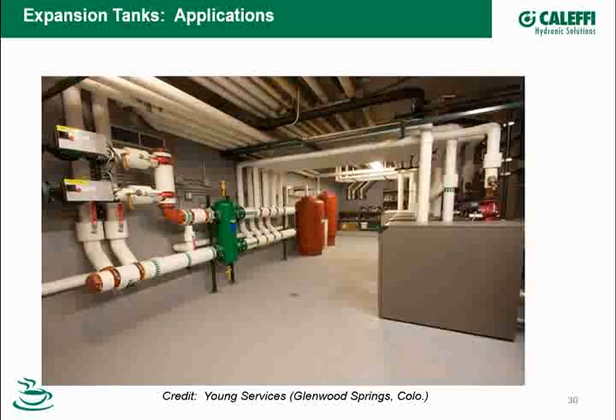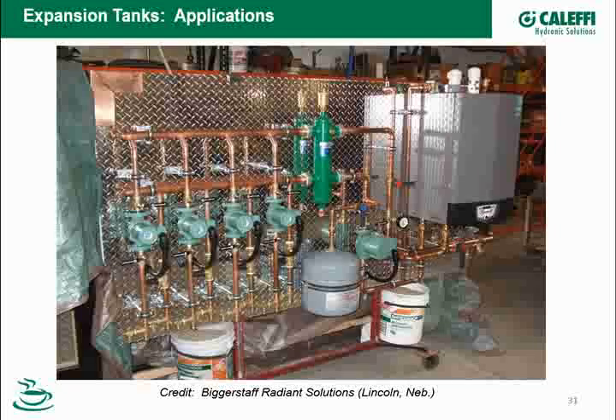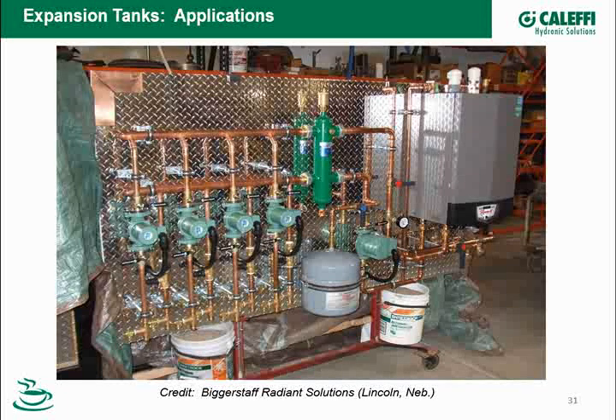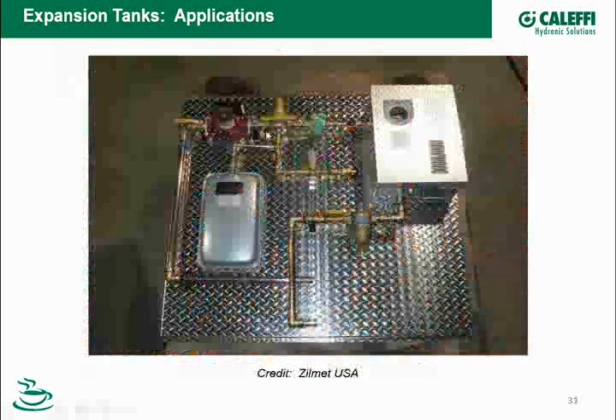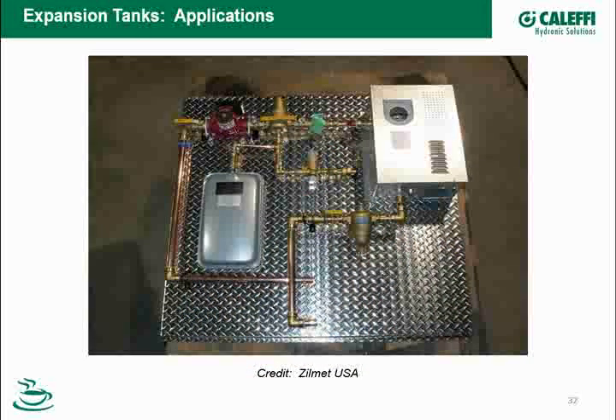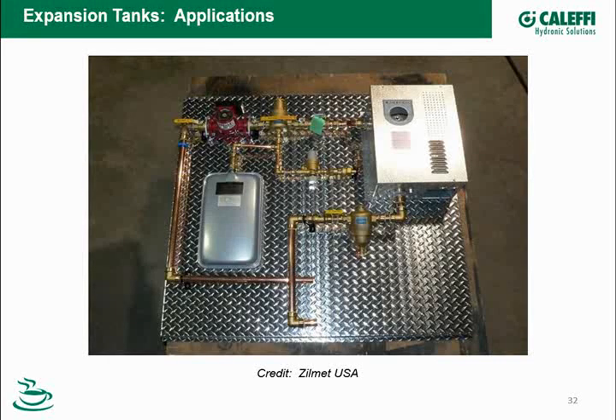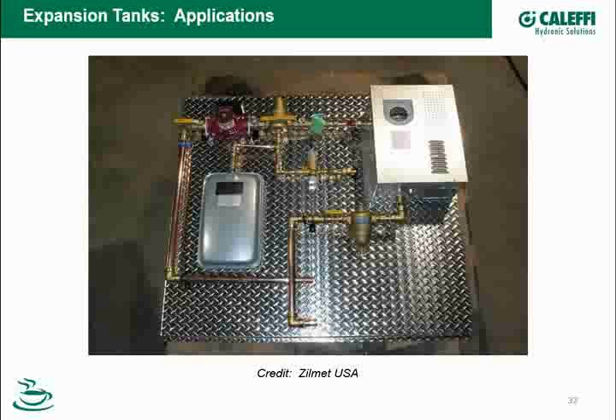Again, same thing on this picture here. I'm going to jump through this one a little bit quick to pick up a little time. And another one here. Here's my pump. Here's my expansion tank tied in here, suction side of the pump. But again, in each one of these installation examples, we're pumping away from that expansion tank, adding the head pressure of the pump to the static pressure of the system.